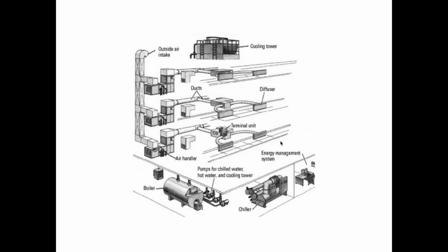How does that work? Well, if that thermostat is satisfied, it only brings a little bit of cold air into this room in the summertime. If it's not satisfied, it opens up a damper and lets a lot more cold air come into this room. So basically the amount of air coming out of that diffuser varies. It's always the same temperature, but the amount varies all the time, right? That's called a variable air volume system.